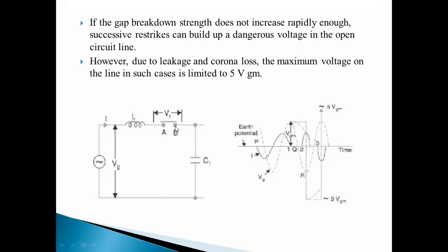when actually this gets disconnected, the circuit breaker previously has closed contacts. Okay, after some time they open, means when the fault occurs, these contacts open there. So when these contacts open, whatever voltage is across the circuit breaker is nothing but VR, and that is the difference between these points A and B. Okay, and this capacitor C1 is connected across this supply.